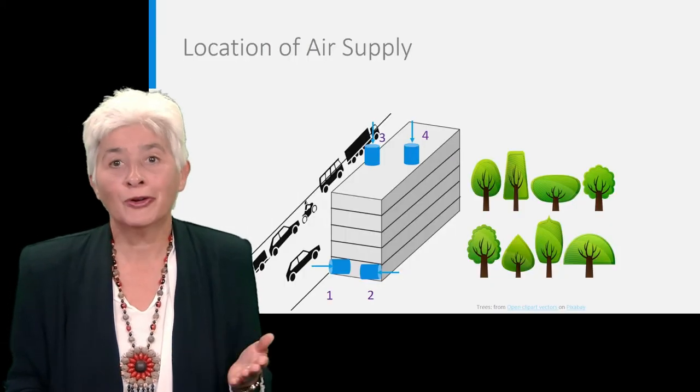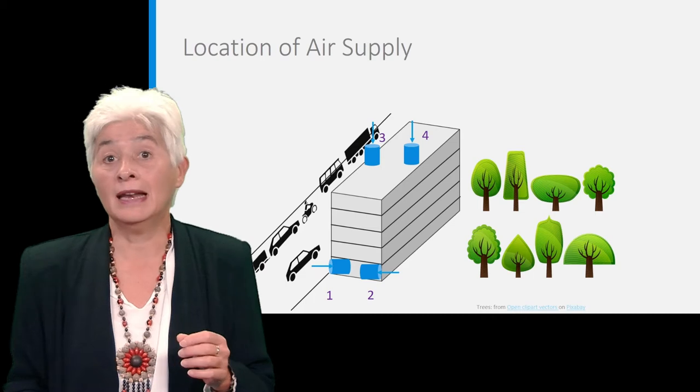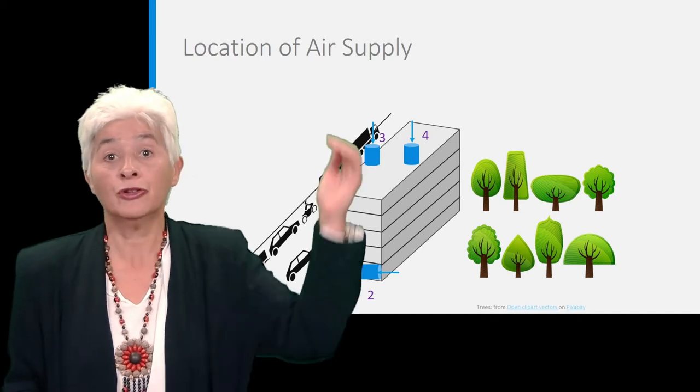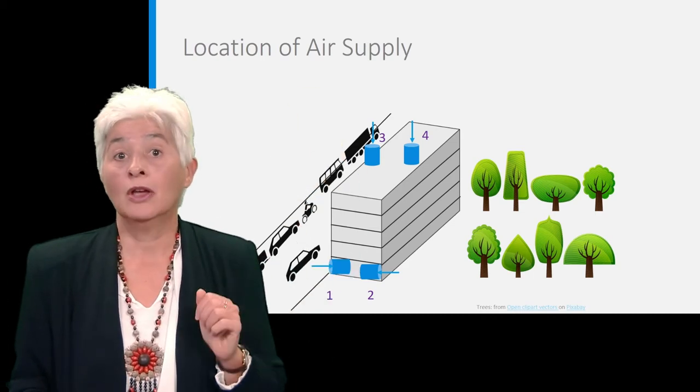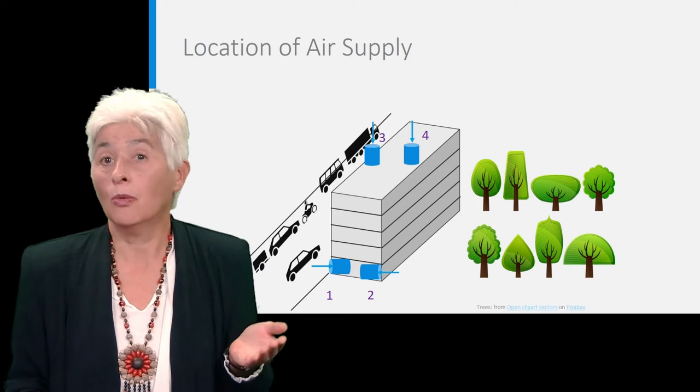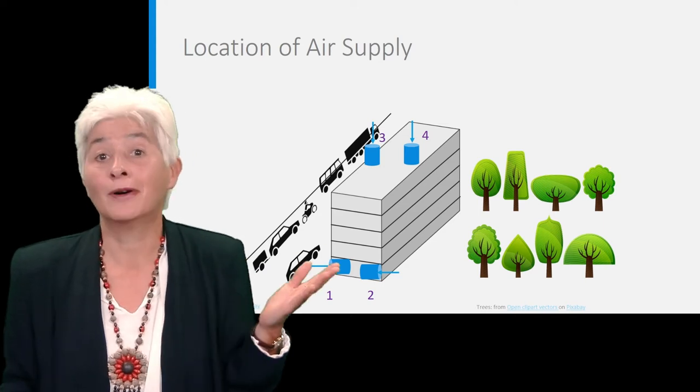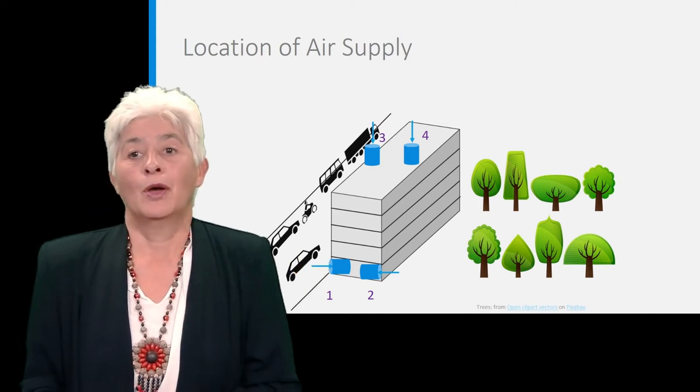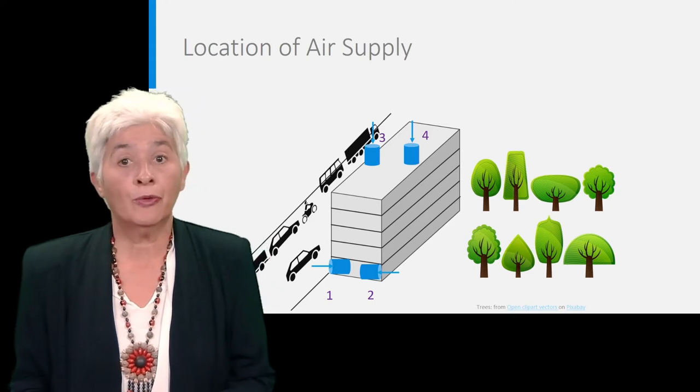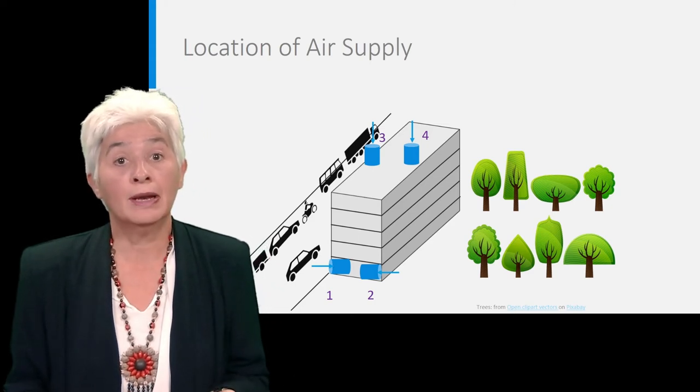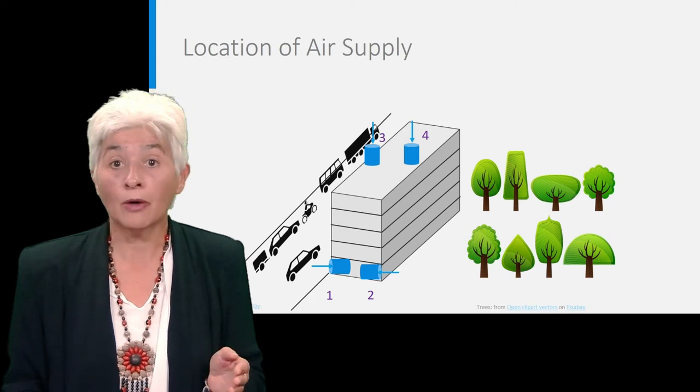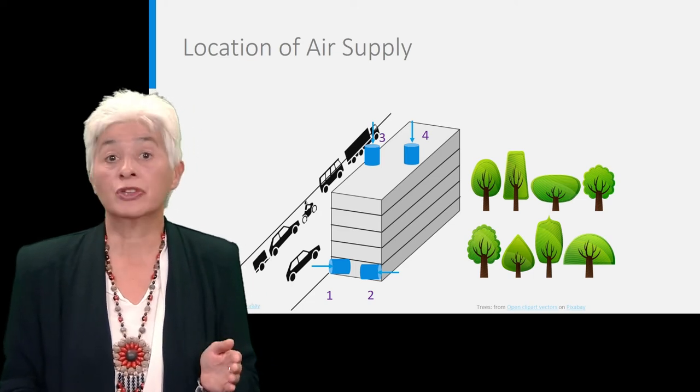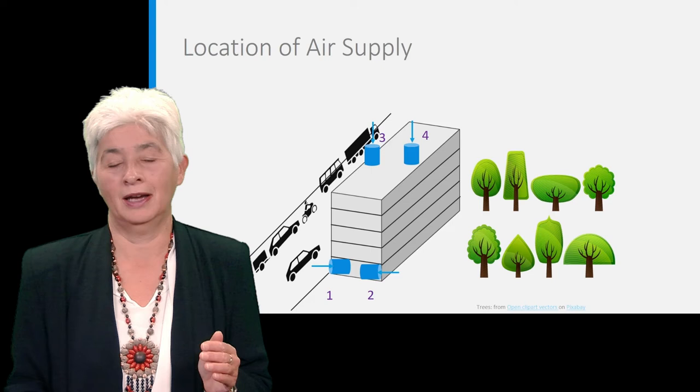Let's start first with the location of the air inlet where the outdoor air is supplied to the air handling unit. Where should we position it? One, two, three, or four? Well, position one is at street level, so a lot of pollution by traffic will enter the building, which is threatening for the quality of the indoor climate. So that's really not a good idea.